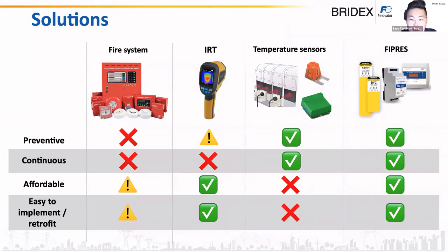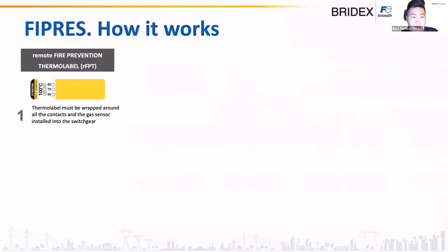FIPRES has all the advantages of the temperature sensors, because it's preventive and continuous, but also it's really affordable, and it's very easy to implement. And the degree of penetration for FIPRES is higher than 90%, which means we can equip 90+% of concerning points inside the electrical panels. And how does it work? Yeah, the main element, or main device, in this system is the Remote Fire Prevention Thermolabel, RFPT.